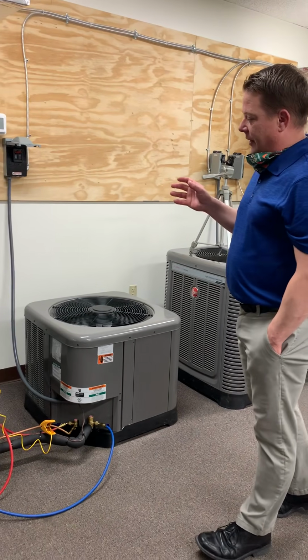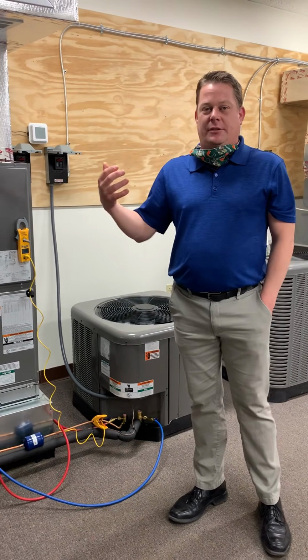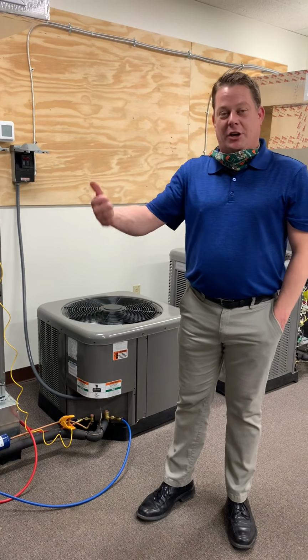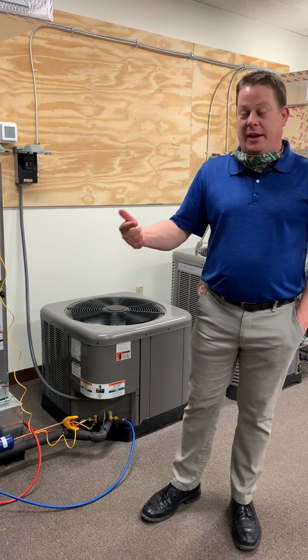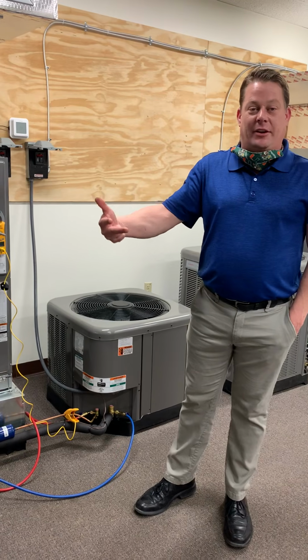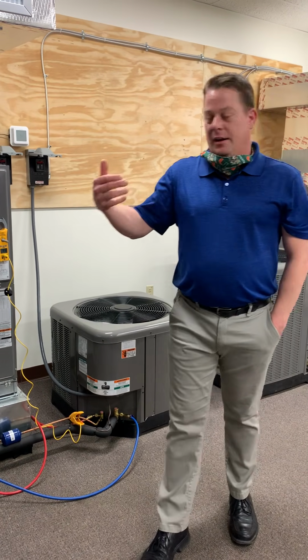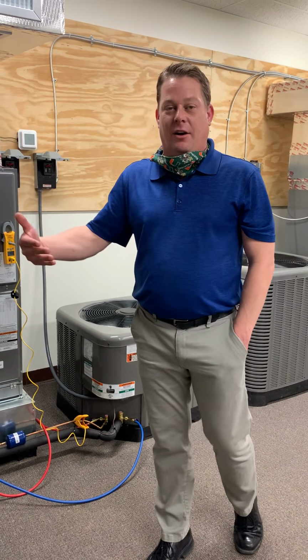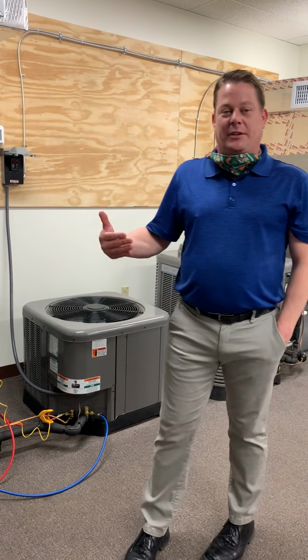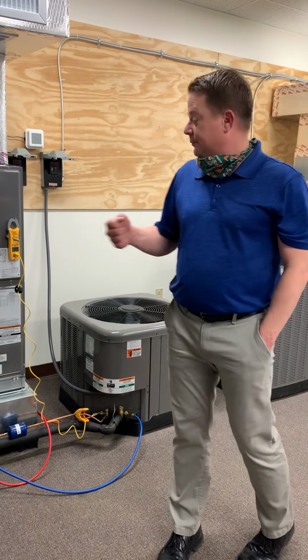So both numbers are very important when you're trying to troubleshoot a system, to know that the charge is right, that the metering device is working right, that we have good airflow. All of these things we need to know to be able to try to diagnose and find out what the root cause of the problem is with our system.